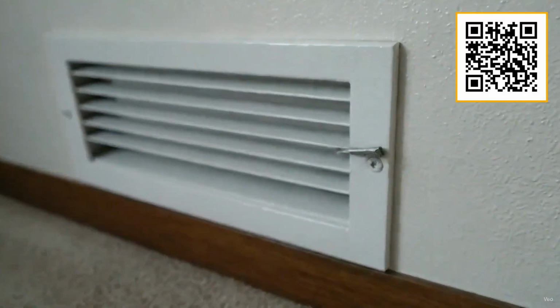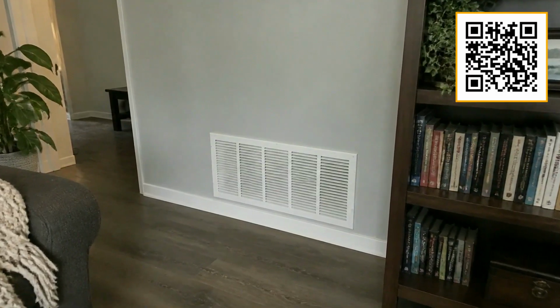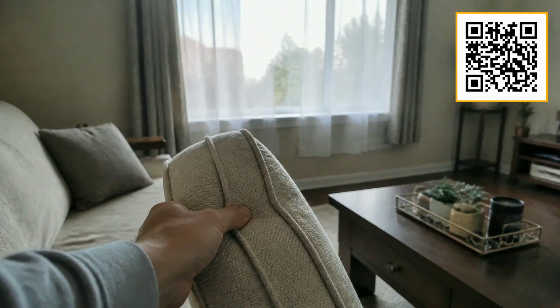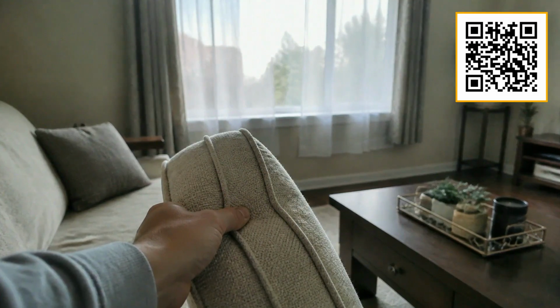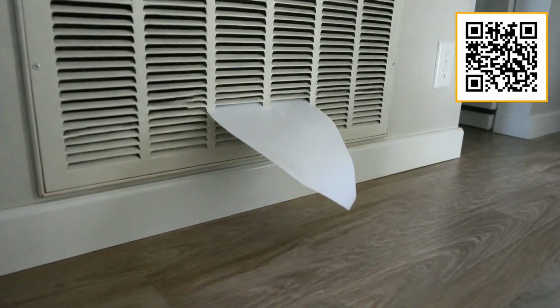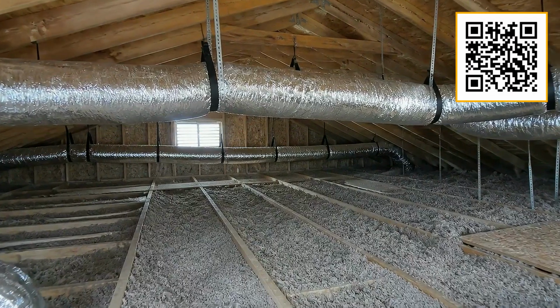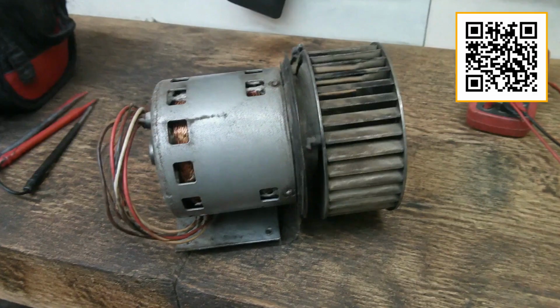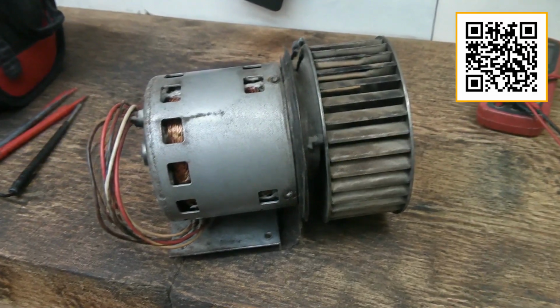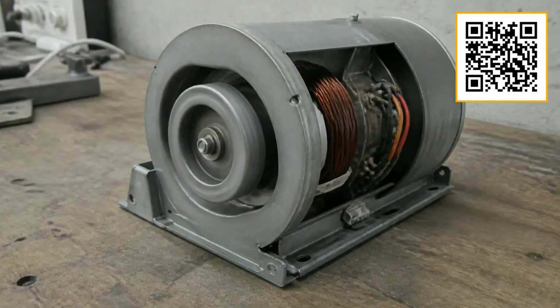Air flows out through the supply registers, circulates through the living space, gets pulled back through the return registers, passes over the evaporator coil or the heat exchanger, gets conditioned again, and goes back around. The pressure inside the ductwork stays within the range the system was built for. The blower runs at its intended load. Everything holds together. The moment you close a vent, you block one of the exits. The blower does not know that. It is still trying to push the same volume of air it always does.